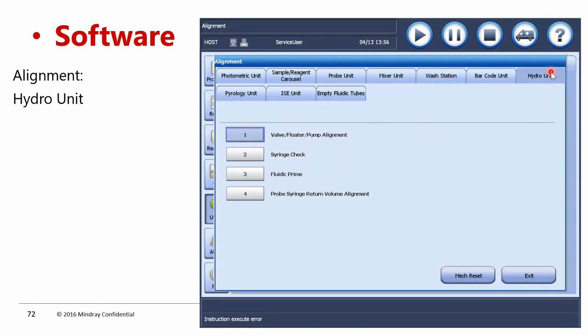So this is a hydro unit. You have four options. You can verify the sensor status, and individually all the valves you can verify, and floating sensors: the DI water tank has a floater, detergent has a floater, and waste also has a floater. So you can verify whether these float sensors are working correctly or not. And the pump alignments, and you can verify the syringe check, whether the syringe has bubbles, whether it is moving smoothly or not, and any jerks are coming, you can observe.